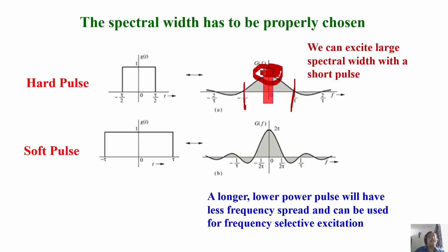This is the spectral width. This is the region of the spectrum you have to choose, and then excite in this region. So all the spins will be excited with uniform power. The uniform excitation is very important. Supposing you excite in this region, you will get some signal, of course. I am not saying you will get nothing, but all the spins are not uniformly excited, and the peaks which are coming in this region may not even get excited at all.